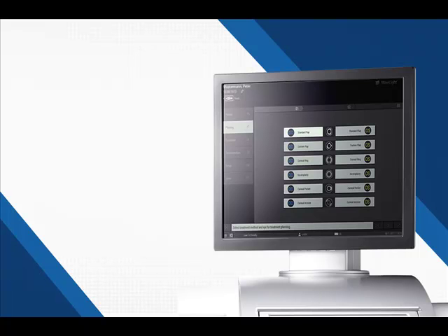Now remember, before I said there is a straight line going across, meaning the eye is flat, you can apply suction. This is an example of that mountain peak. You can see that the eye is not flat, the eye is quite off angle, and you do not want to proceed with applying suction. You should lift the laser. Again, explain to the patient what they should be doing. They should be looking at the red fixation light, and then try again.